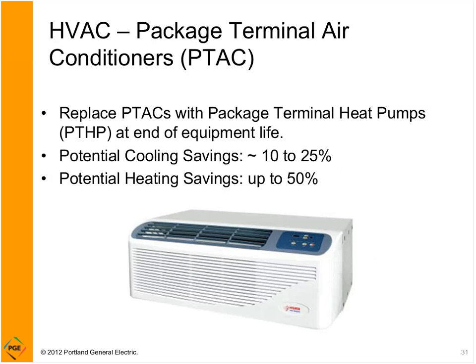Package terminal air conditioners, or PTAC units. These are often seen in hotels and motels and sometimes in really any type of commercial building, even an office space. The typical package terminal air conditioner does have electric heat in the form of strip heat. So if you replace these with a heat pump, you're going to get a big efficiency gain on the heating side and potential to get a benefit on the cooling side as well. So cooling savings 10 to 25%, and potential heating savings up to 15%, or 50%, excuse me.